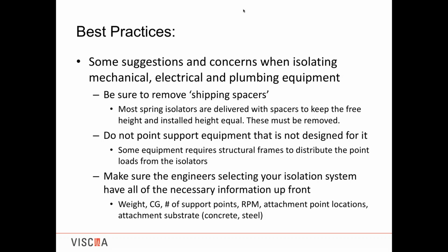Another issue you have to always concern yourself with is point support. Now, I have a picture later on to describe it, but in general, some equipment is not designed to have a spring or some isolator point at its base at a discrete point. It needs distributed loading so it doesn't buckle, doesn't collapse. And it's the manufacturer of the equipment who determines that. Those that require continuous support will send out some submittal cut showing this. You need to look for it, and if the manufacturer says so, you need to follow his instructions. If it wasn't designed for point support, you will have structural issues with the equipment after installation.